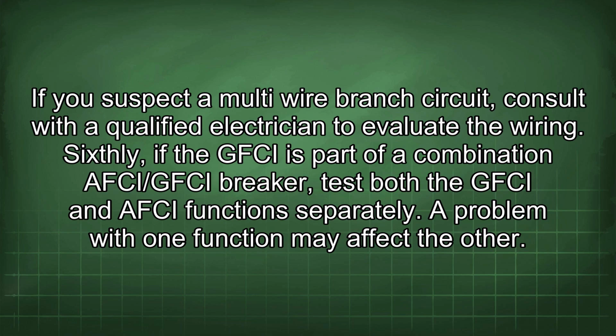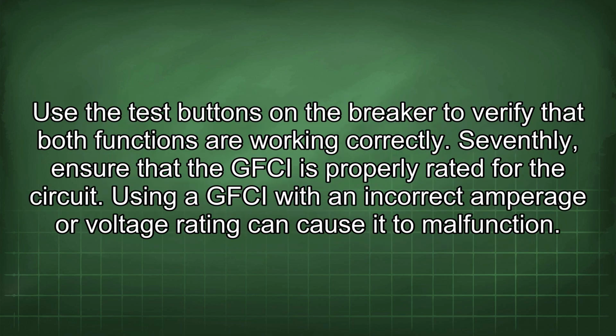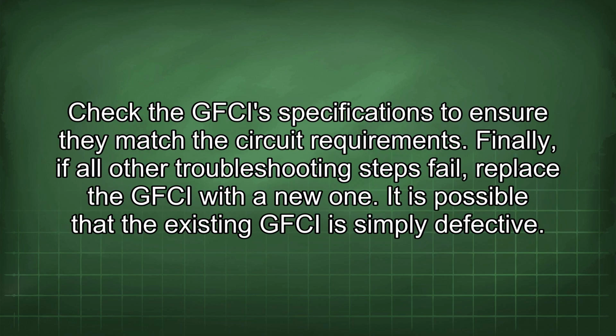Sixthly, if the GFCI is part of a combination AFCI/GFCI breaker, test both the GFCI and AFCI functions separately. A problem with one function may affect the other. Use the test buttons on the breaker to verify that both functions are working correctly. Seventhly, ensure that the GFCI is properly rated for the circuit. Using a GFCI with an incorrect amperage or voltage rating can cause it to malfunction. Check the GFCI's specifications to ensure they match the circuit requirements.